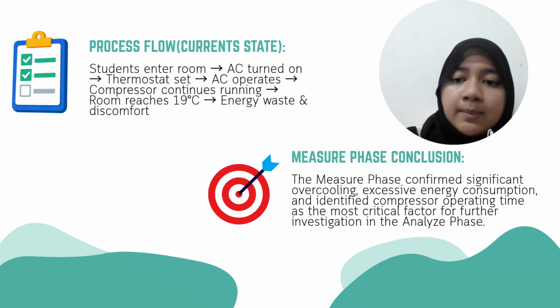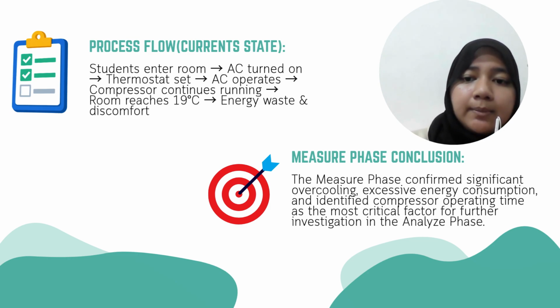In conclusion, the measure phase confirmed that overcooling is happening in the lecture room. The main issue is the compressor running for too long. This problem will be studied further in the analyze phase.